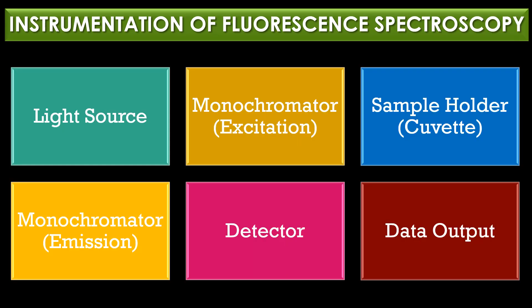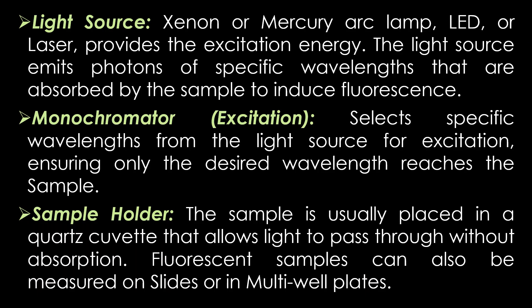The instrumentation of fluorescence spectroscopy contains six major parts: light source, excitation monochromator, sample holder, emission monochromator, detector, and data output. The light source — usually a xenon or mercury lamp, LED, or laser — provides the excitation energy. It emits photons of specific wavelengths that are absorbed by the sample to induce fluorescence.